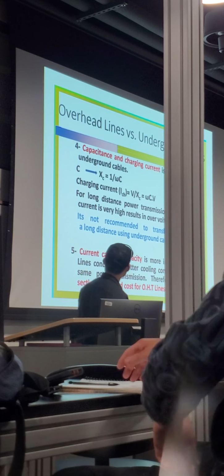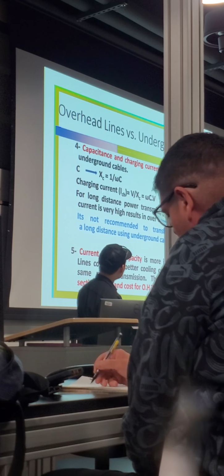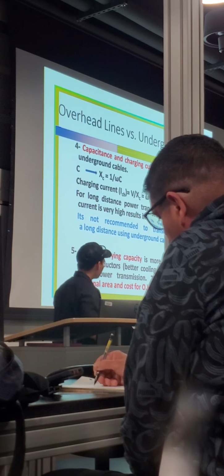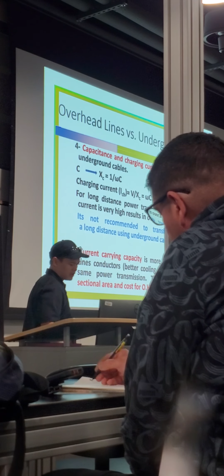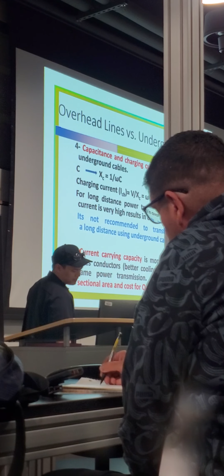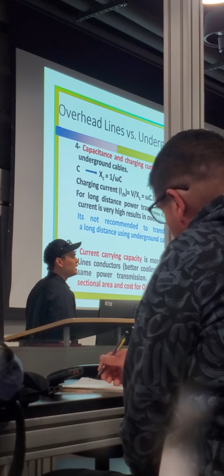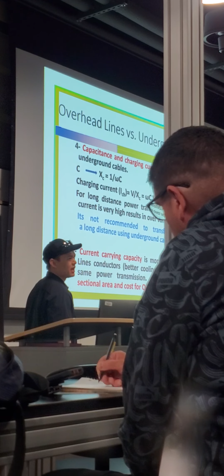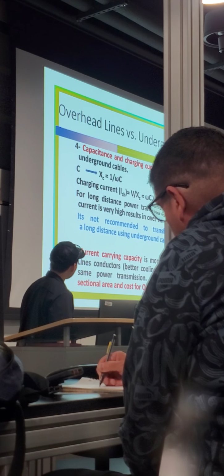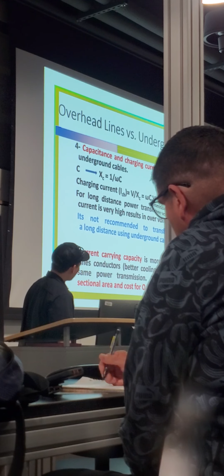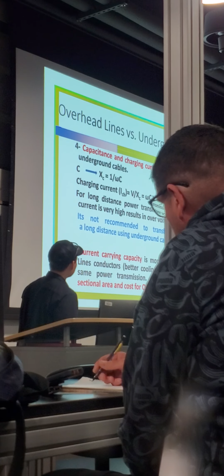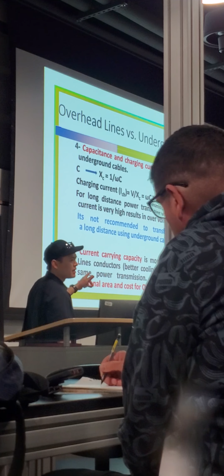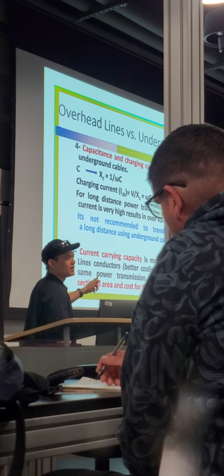For long distance power transmission, the charging current is very high, resulting in overvoltage problems, so it's not recommended to transfer power long distance using underground cables. That's why you'll see transmission lines all along, say, PCH, on that scenic route. Current carrying capacity is more in the case of overhead transmission line conductors, because of better cooling conditions. Anybody want to guess why that is?